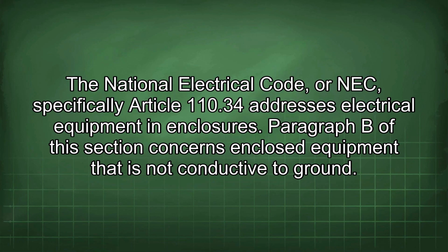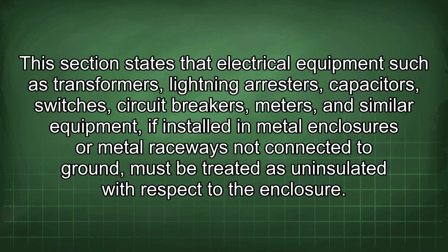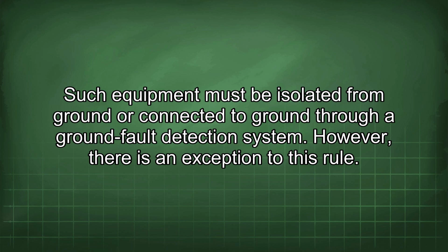The National Electrical Code, or NEC, specifically Article 110.34 addresses electrical equipment in enclosures. Paragraph B of this section concerns enclosed equipment that is not conductive to ground. This section states that electrical equipment such as transformers, lightning arresters, capacitors, switches, circuit breakers, meters, and similar equipment, if installed in metal enclosures or metal raceways not connected to ground, must be treated as uninsulated with respect to the enclosure. Such equipment must be isolated from ground or connected to ground through a ground fault detection system.